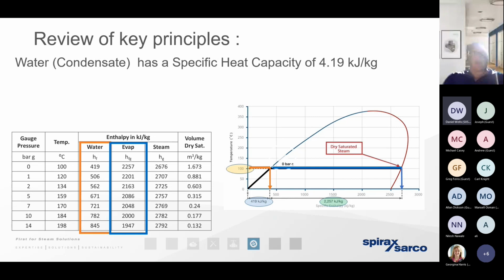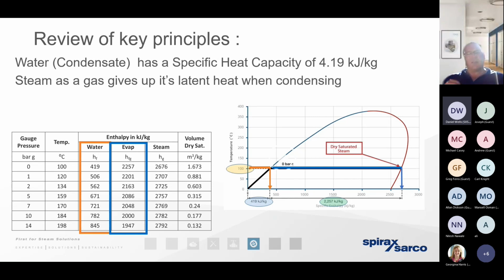And the next column, highlighted in blue, really emphasizes the energy that we then need to add to that boiling water to make it fully evaporate, boil off, and change state from a liquid to a gas. We call that the enthalpy of evaporation. And you can see there's a significant amount of energy we need to add to that already boiling water in order for it to do that. But the thing here is that energy isn't lost. The steam carries that energy and gives it up at the process, at the heat exchanger. It's the same energy that we add to the boiling water to make it change state. It's that same energy that passes across the thermal barrier into the process. So think of that as the useful heat energy.